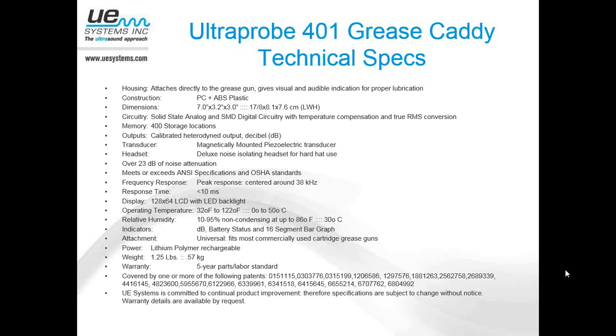So how would someone know if it's a lubrication problem they're hearing or a failing bearing? What's the difference there? Yep, so that kind of gets into ways that we teach people to set baselines and alarm levels. So really the preferred method of setting a baseline when it comes to using ultrasound is through an approach we call the historical method. So in the DMS software, you set up your route, and then you just begin to go out and collect data. So you're building a history.